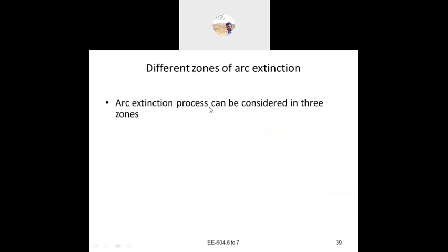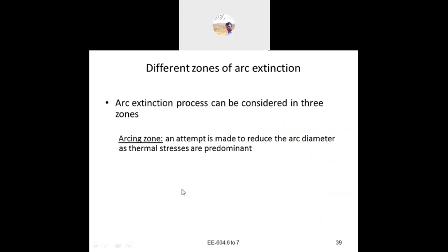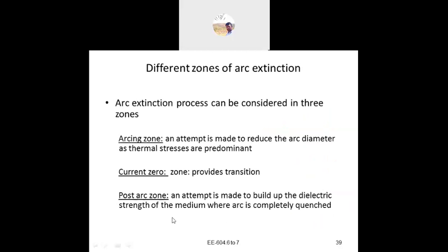So next, different zones of the arc extinction. What are the different zones? The arc extinction process can be considered in three zones. That is the arcing zone, next the current zero zone, and next the post arc zone.